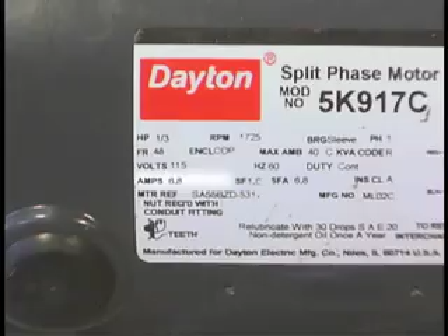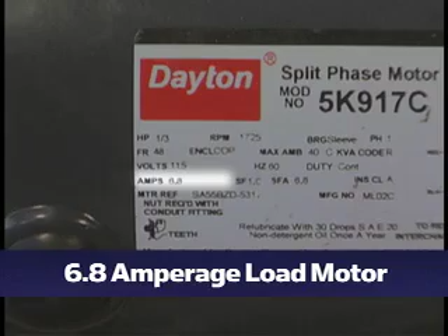With this meter, we're showing the amperage that's being drawn onto the board to support the devices on the board, the meters, our unit, and a Dayton motor. This motor is labeled at 6.8 amps, and again, very typical of inductive loads in a home. With the unit off, the board is drawing 5.7 amps, and the motor is drawing 5.7 amps. So we have a fairly balanced load.